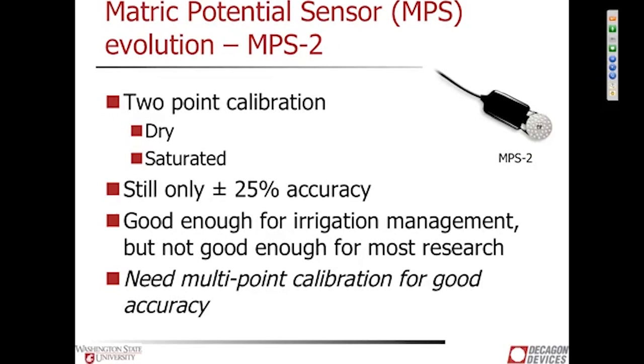So the second generation was the MPS-2, and the MPS-2, as the name indicates, had a 2-point calibration where we calibrated the sensors dry and we calibrated them in a vacuum saturated state, and that helped quite a bit, but we still had only plus or minus 25% accuracy.